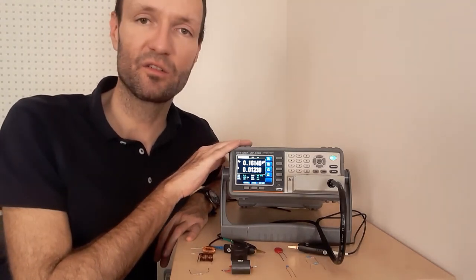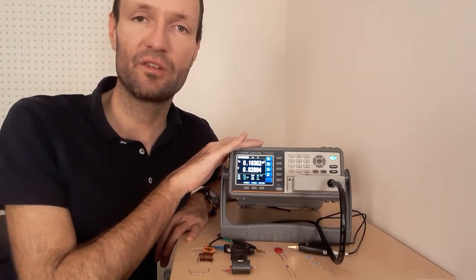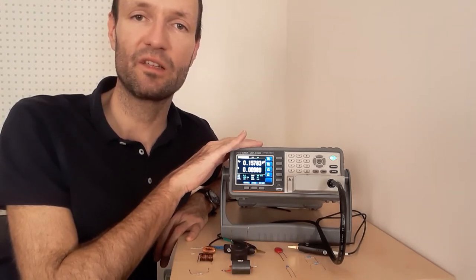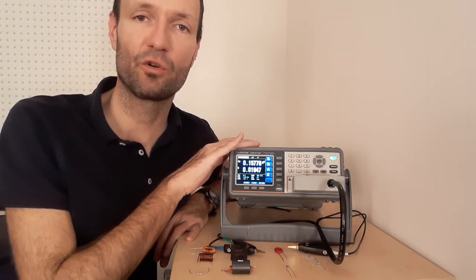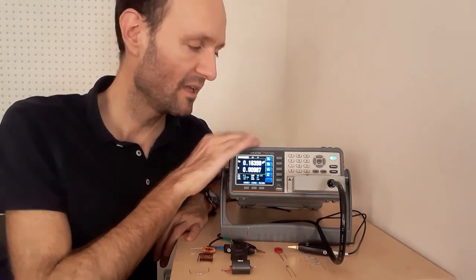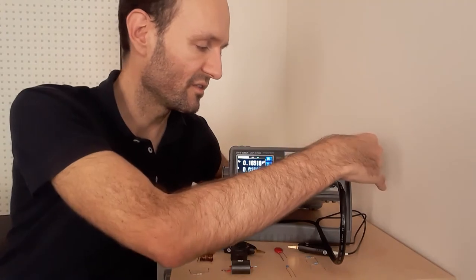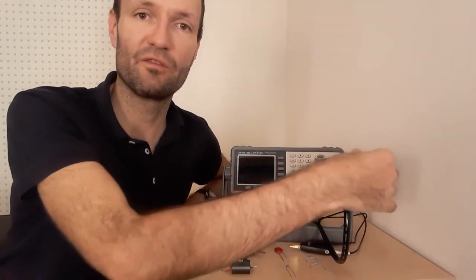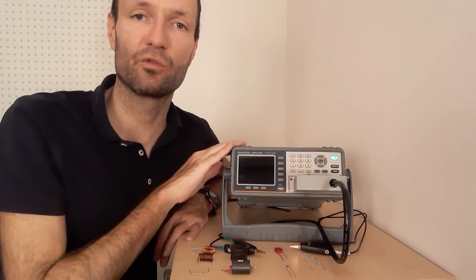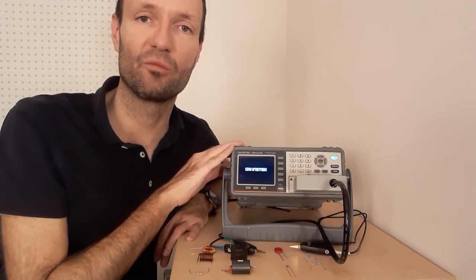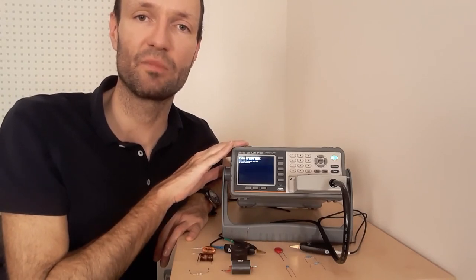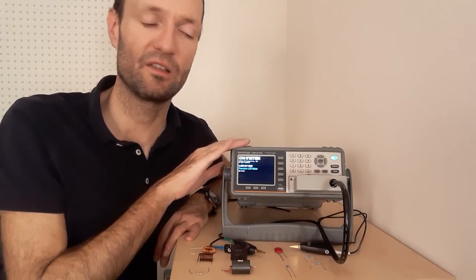If you get stuck somewhere, if the measurement device does not behave as intended and is showing some strange stuff on the display, just switch it off, wait for five seconds and switch it on again and it should go back into some basic mode. As said, there is no preset button here on this device.